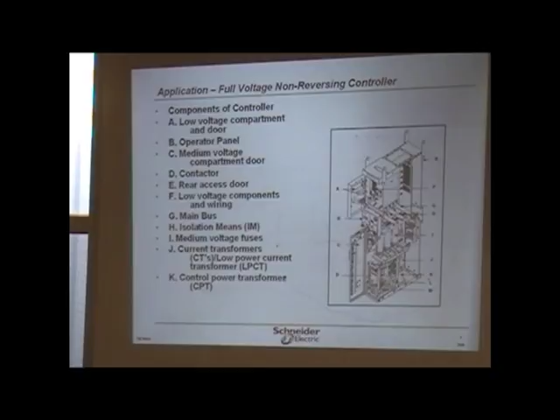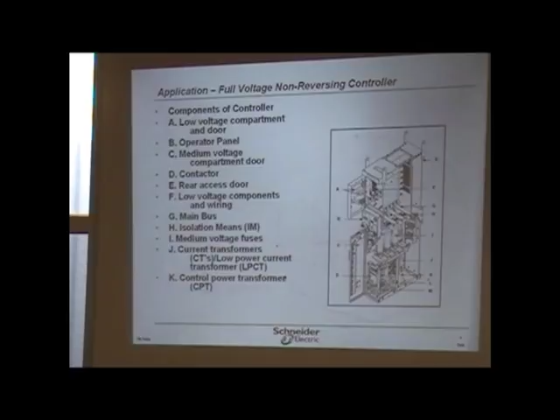But when you isolate it, the switch, or this isolating means, is a no-load interrupter, meaning you have to kill your load downstream before you open this up. Because essentially, think about that switch you saw in the switch yard, when you're opening it under load. If you have a load downstream, that kind of damage could occur, even though it's supposed to be in a vacuum or whatever as far as that isolating means.